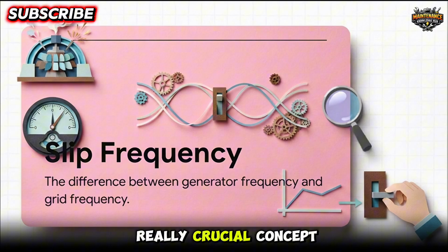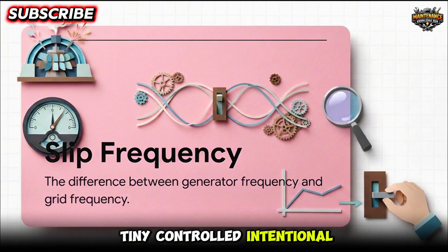Now there's a really crucial concept here called slip frequency. Remember those numbers we just looked at, where the generator was at 50.02 Hz and the grid was right at 50.00? Well, that tiny 0.02 Hz difference is the slip frequency. And here's the cool part. It's not an error. It's actually a tiny controlled intentional drift.